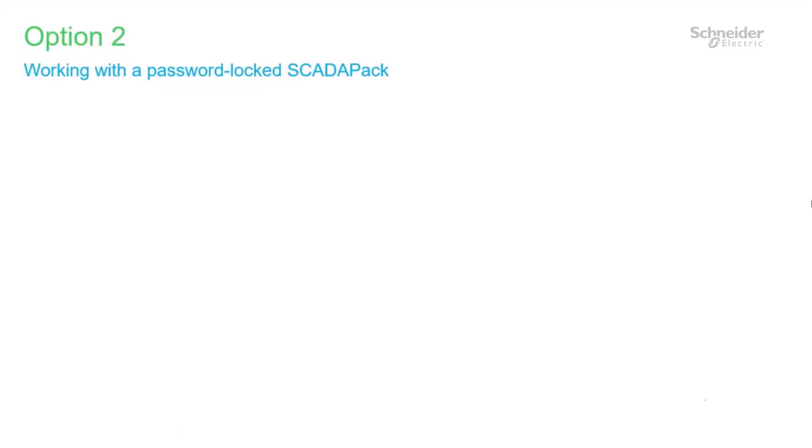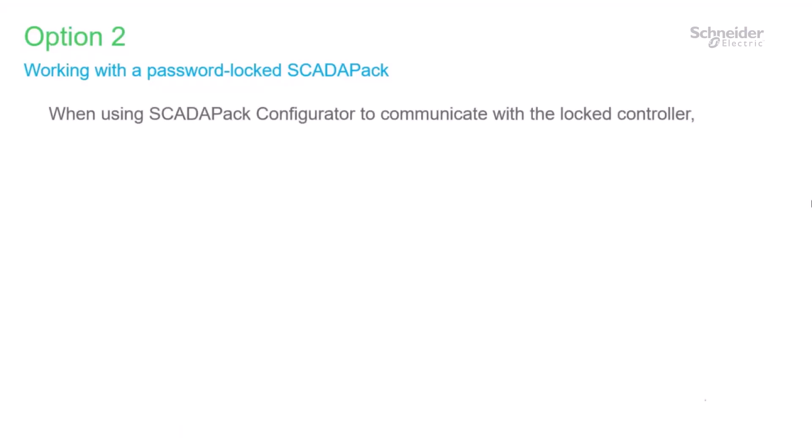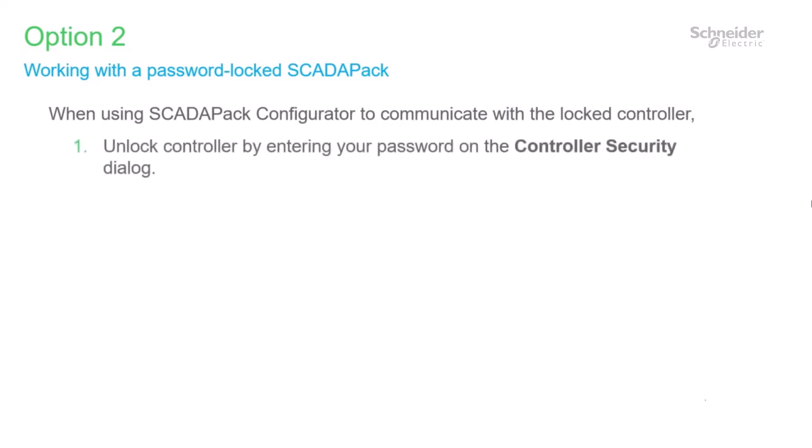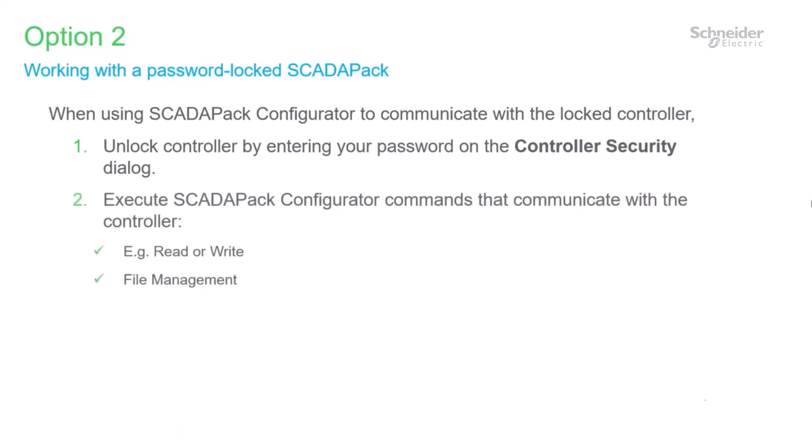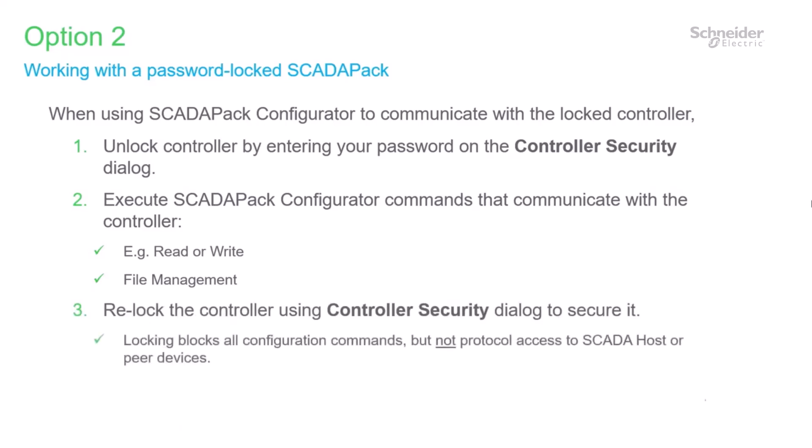Summarizing how to work with a password locked SCADA pack. Whenever you're using SCADA pack configurator to communicate with your controller, when it's locked, the first thing you need to do is unlock it by entering the password on the controller security dialog. Then you can execute all the commands you need to, like read and write of the configuration or file management. Then you relock the controller using the controller security dialog to secure it. Note that locking blocks all configuration commands, but not protocol access to the SCADA host or peer devices.